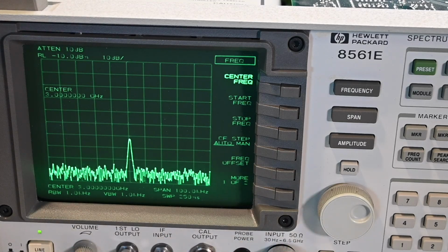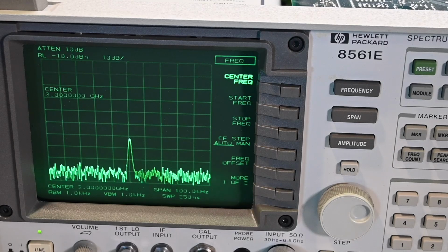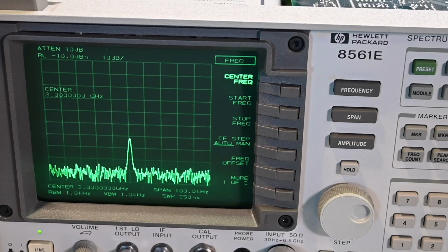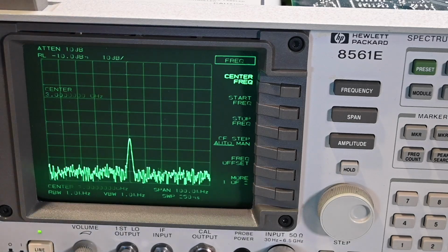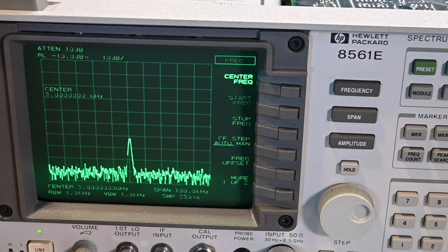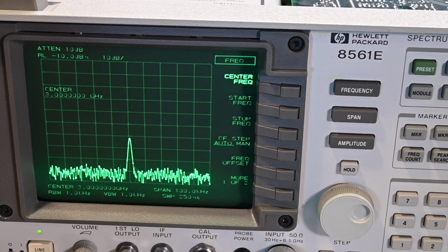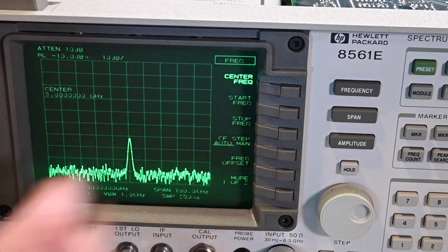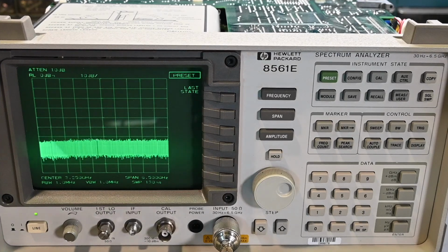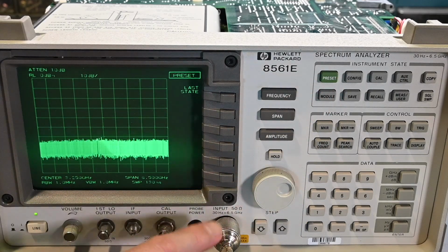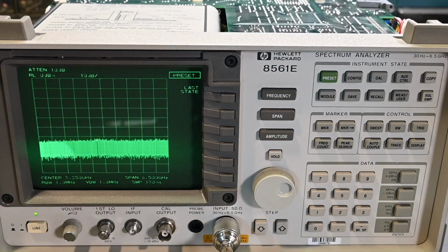And then they want you to move the write protect enable jumper on the A2 controller circuit board to the write enable position. So I'm going to reach around to the side and I'll get that jumper moved over into the write enable position so that we can make the changes to the calibration constants. Okay, so the write protection jumper is moved over to the write enable position, and I did a preset on the instrument, so that just gets it to a known state. And the input here is 3 gigahertz at exactly minus 10 dBm. I adjusted the signal generator like I showed before, so it allows for the loss that's in the cable.